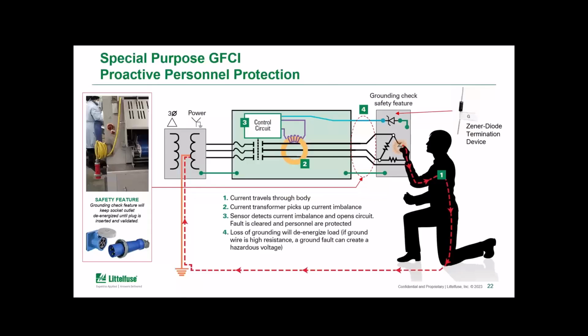A special purpose GFCI must also check the validity of the equipment grounding conductor. It's shown on the slide here with that blue conductor at the top of the drawing, and sometimes that's referred to as the pilot wire or ground check wire. The device uses that conductor to measure the resistance in a loop from the device out to the equipment through a termination device and then back to the special purpose GFCI on the ground wire. So this resistance is monitored to ensure that the equipment grounding conductor is intact and there's a valid low resistance path. If that grounding conductor goes open circuit, the unit will de-energize and remain tripped until that grounding connection can be reconnected.